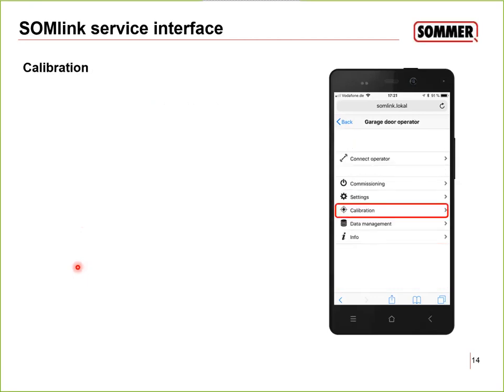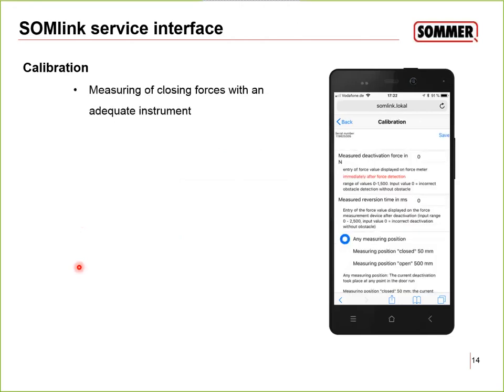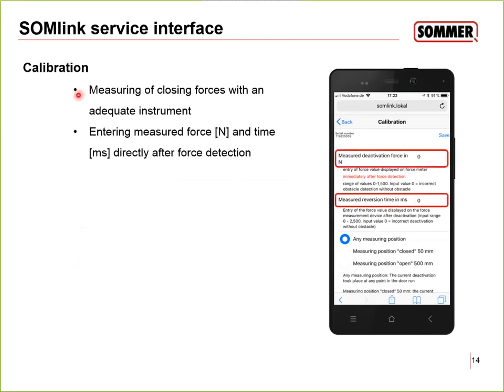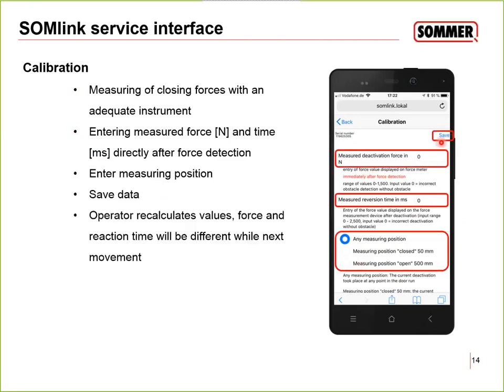Next point is calibration. So after the installation, usually you do a measuring of the closing force with an instrument, and you should be below 400 Newton. This is the rule. And if you are maybe above 400 Newton, you could enter the Newton over here, maybe 430 Newton, and the milliseconds, the reaction time. And then the operator, the next is you enter the measuring point, and then you save the data. That's always important to go on save, because just then the data will be sent to the operator, and then the operator recalculates the values and tries by itself. So for example, by reducing the speed to get below the 400 Newton.